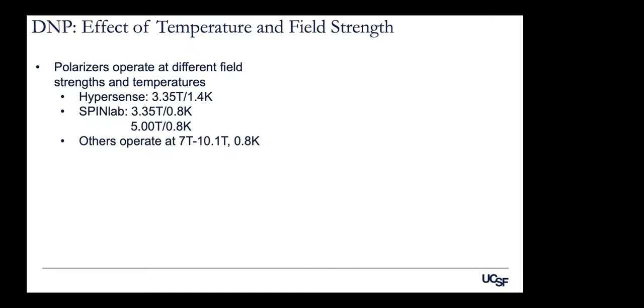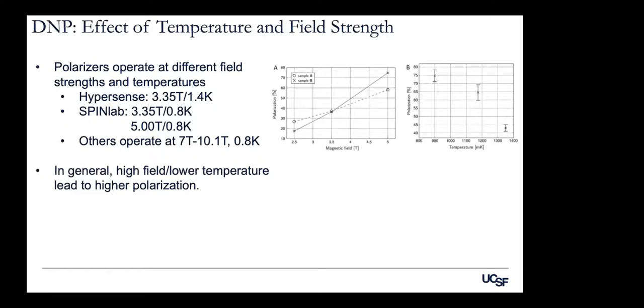Polarizers operate at different field strengths and temperatures. The Hypersense operates at 3.35T and approximately 1.4K. SpinLab systems designed for clinical use operate at higher fields — 5 Tesla — and lower temperature of 0.8K. Other hand-built polarizers go to even higher fields. In general, increasing the operating field and decreasing the temperature lead to higher polarization. Increasing magnetic field gives an increase in polarization, and decreasing temperature also gives an increase in polarization.